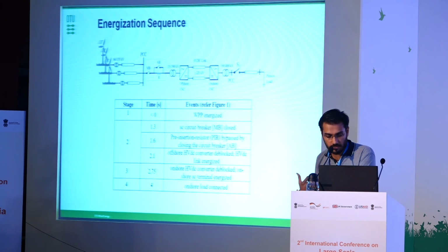So the sequence is as follows: the wind power plant starts grid forming the offshore collector grid, then the main breaker is closed, and after some delay the PIR is bypassed to deal with the transformer inrush. Then at 2.1 seconds the offshore MMC is deblocked, ultimately controlling the HVDC link. Once that is done, the onshore MMC is deblocked, which controls the onshore grid, and then the passive onshore load is picked up.